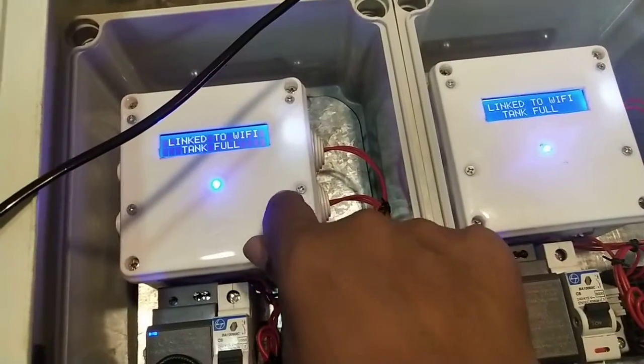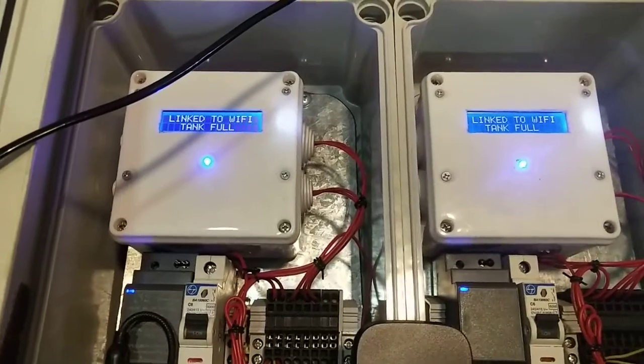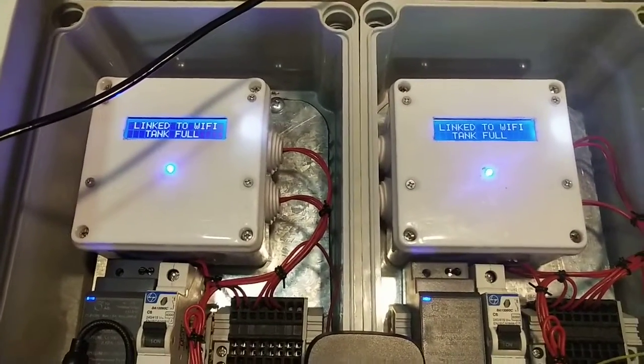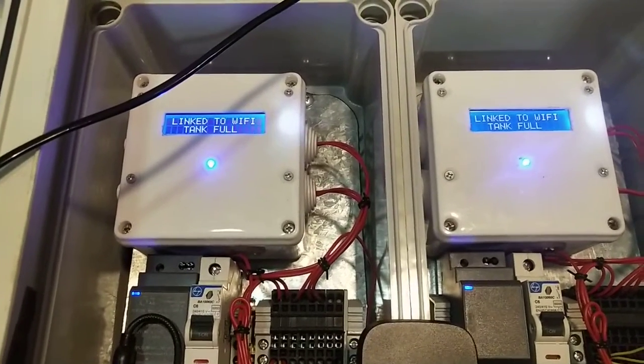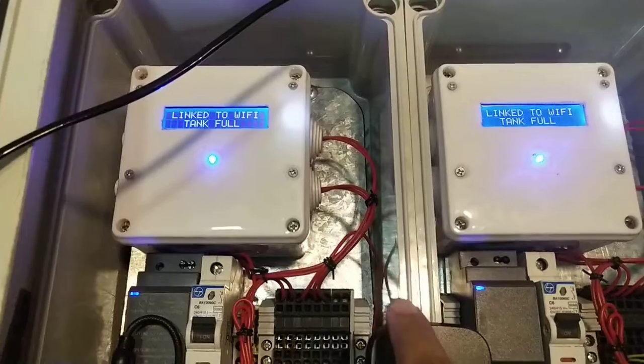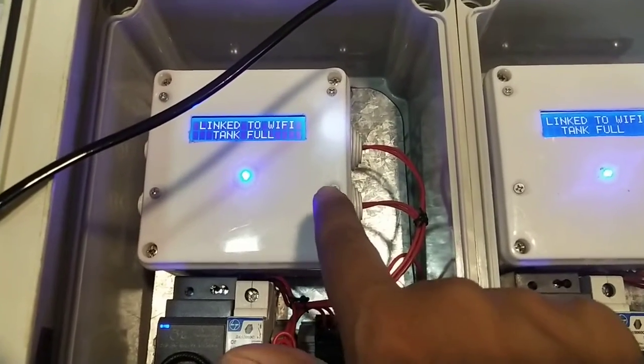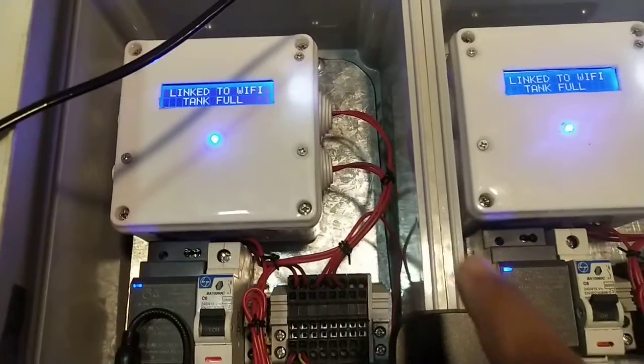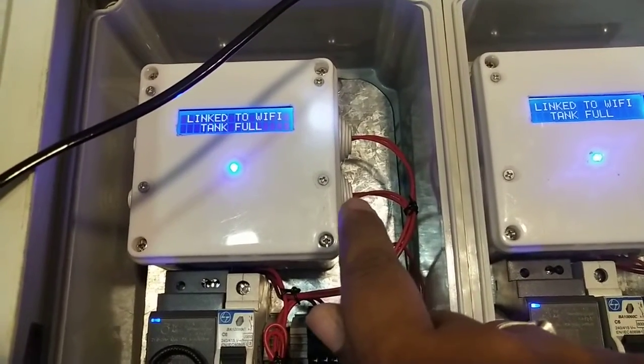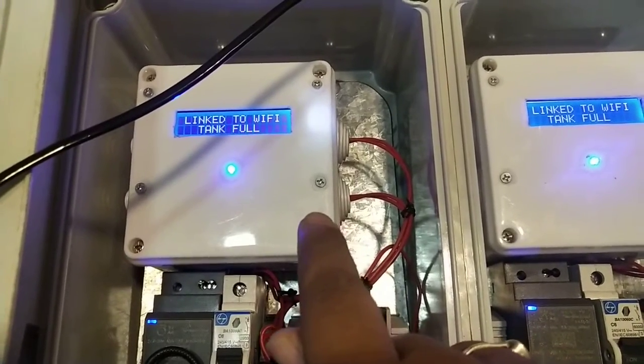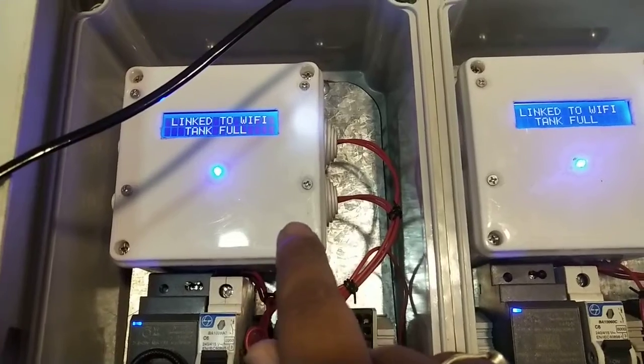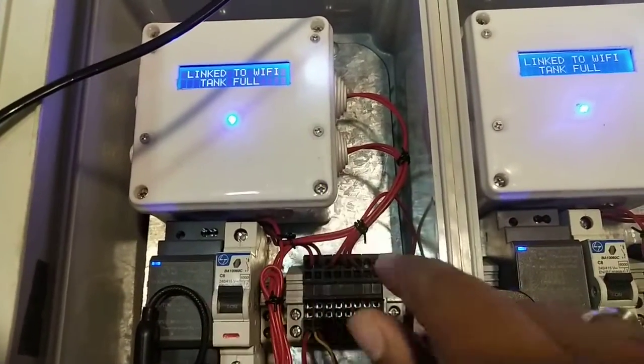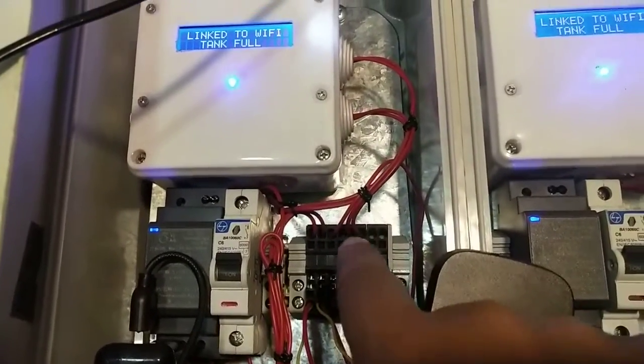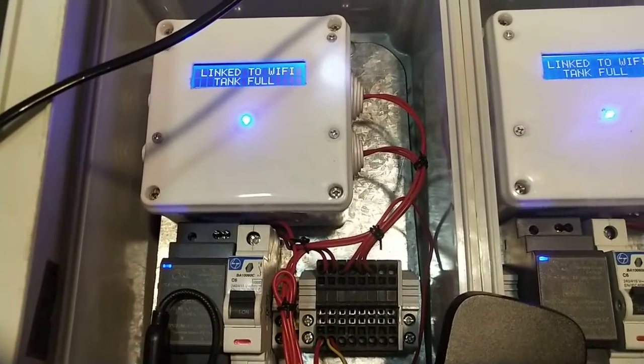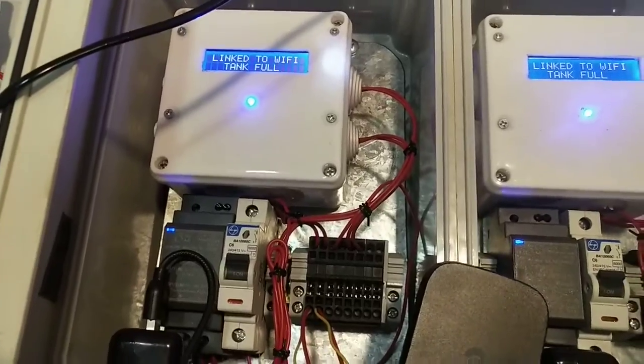There is a relay inside this U-link which is getting activated periodically at an interval of 1 minute to break the motor circuit. If I hold my phone here for about a minute or so, you could hear a small click sound, which indicates that the relay got activated for 2 seconds, then again got deactivated. So that NC output here would break the pump starter circuit, and the pump would stop.